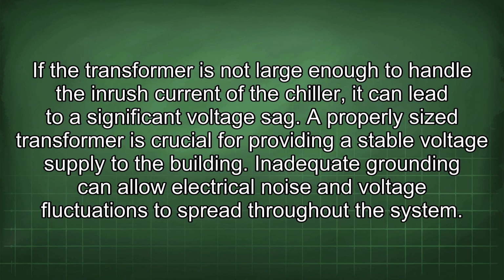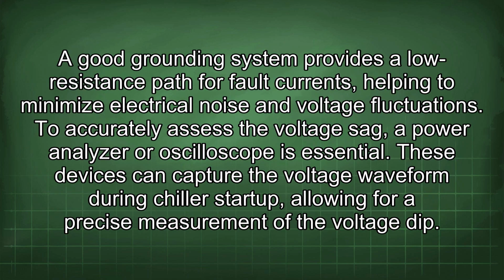If the transformer is not large enough to handle the inrush current of the chiller, it can lead to significant voltage sag. A properly sized transformer is crucial for providing a stable voltage supply to the building. Inadequate grounding can allow electrical noise and voltage fluctuations to spread throughout the system. A good grounding system provides a low resistance path for fault currents, helping to minimize electrical noise and voltage fluctuations.